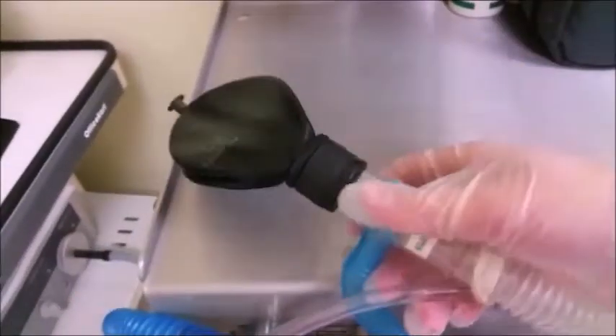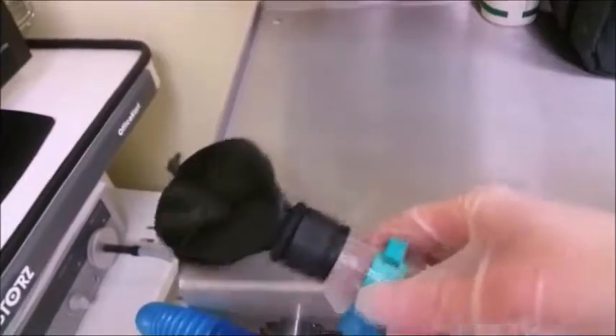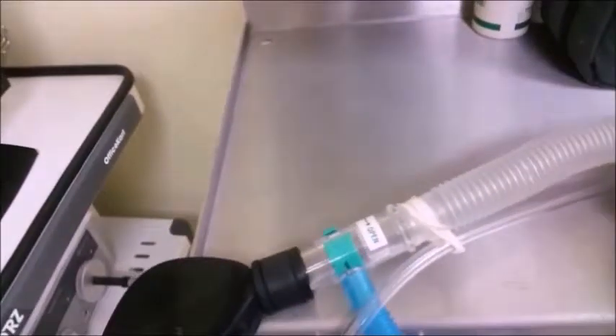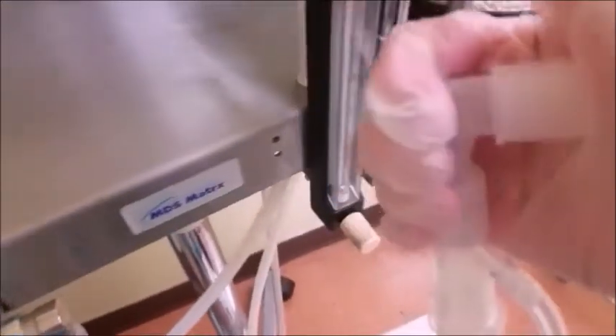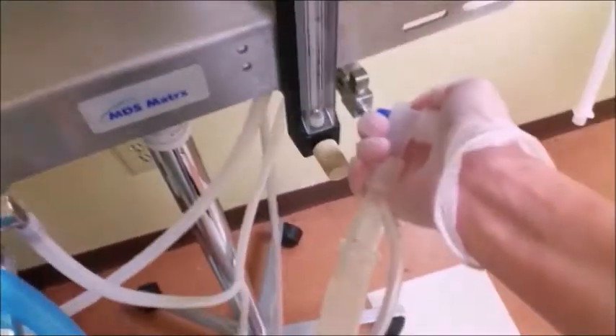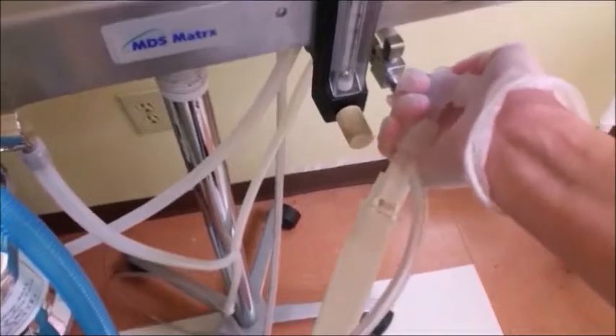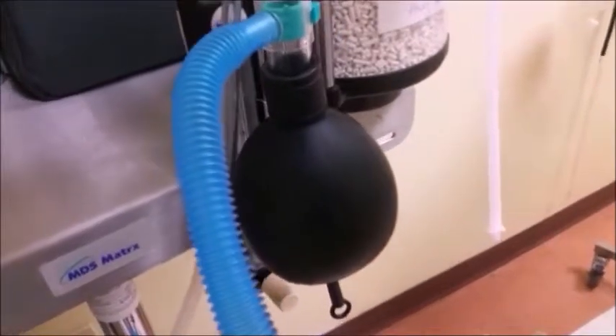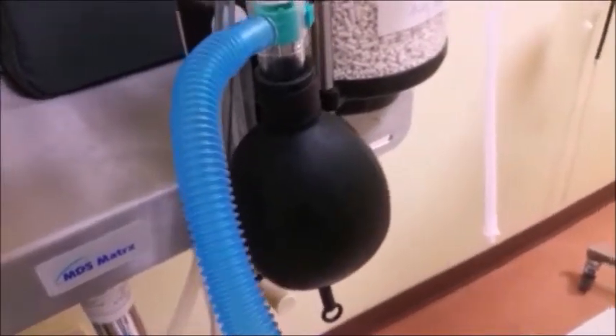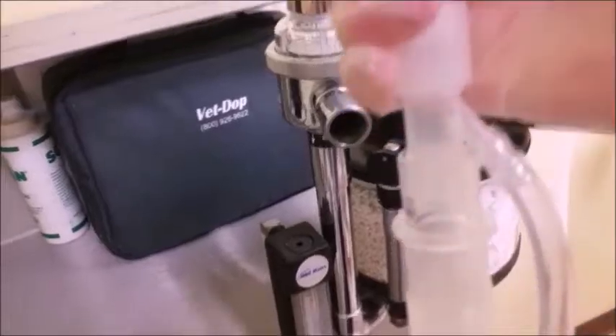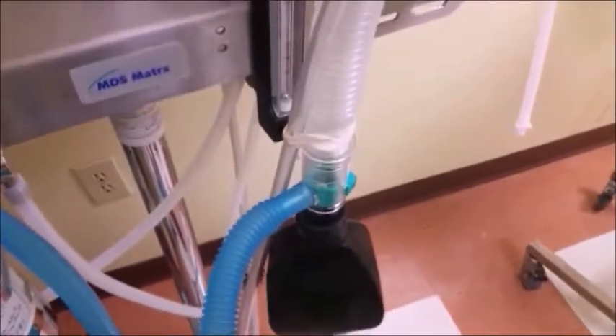So if we are to run a leak test on the system, again, we close our pop-off valve. I cap off the end of our piece, use our oxygen flush, and our bag should be holding its charge, which it is, until I release, and then the oxygen is released.